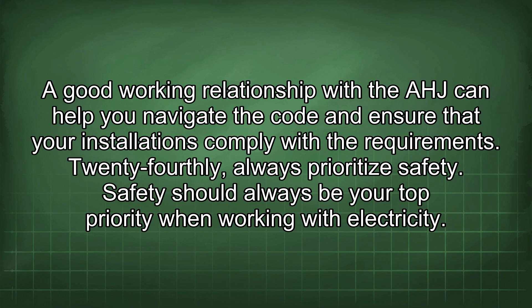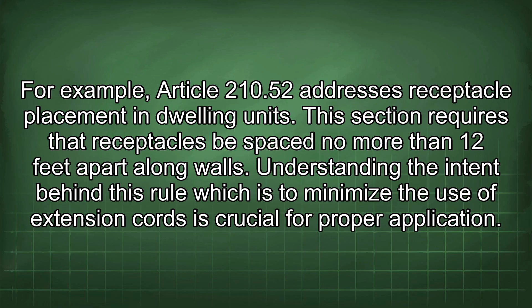25th, consider specific examples of code interpretation. For example, Article 210.52 addresses receptacle placement in dwelling units. This section requires that receptacles be spaced no more than 12 feet apart along walls. Understanding the intent behind this rule, which is to minimize the use of extension cords, is crucial for proper application.